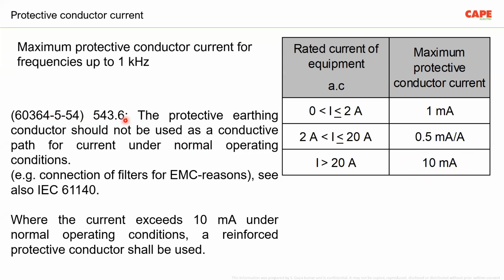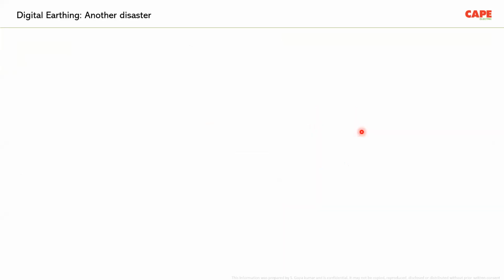IEC 60364 says the protective earthing conductor should not be used as a conductive path for current under normal operating conditions. Of course, during a fault it can flow, but not during normal conditions. When the current exceeds 10 milliampere under normal operating conditions, a reinforced protective conductor shall be used. Basically, we are supposed to make additional safety measures, but don't look at the slide that way. What is important is that the maximum current which can flow continuously in a PE conductor is a few milliamps. Now look at the digital earthing. I would say it's a digital disaster.